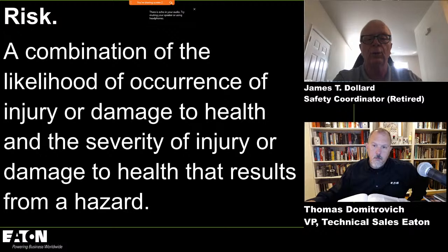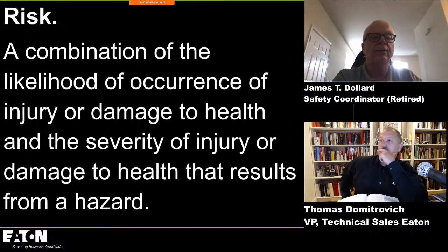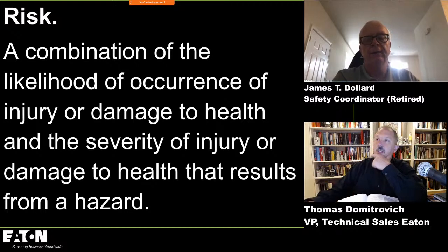So what we have to do is first take a look and ask, is there a hazard? Is there a shock hazard? Well, first we look at the likelihood of shock. We look at the likelihood of occurrence, and then we take a look at the severity of injury. If we've got a bell battery, that's one thing, and we can't get hurt. If we've got a 277-volt circuit, that's going to be completely different. And then we roll risk into the definition of risk assessment, and that's next. All right.